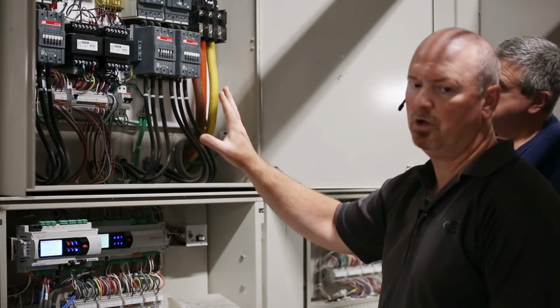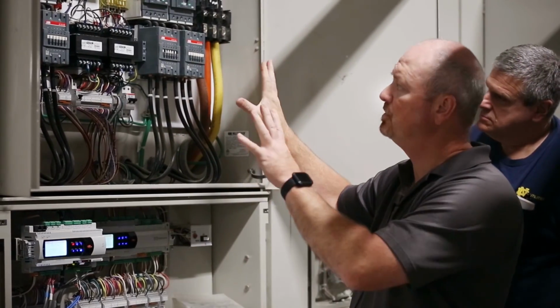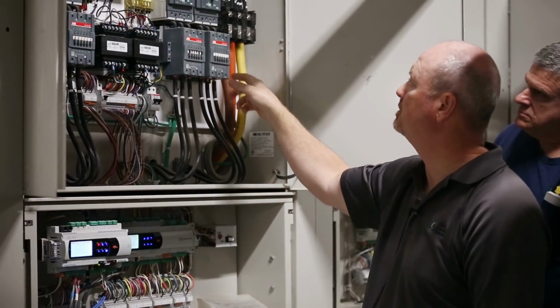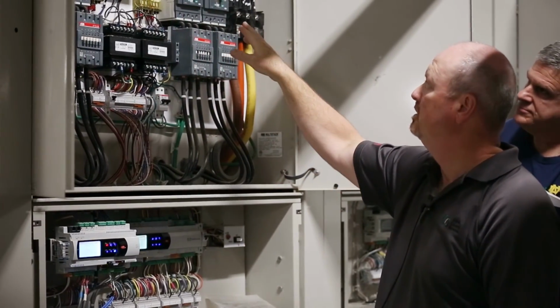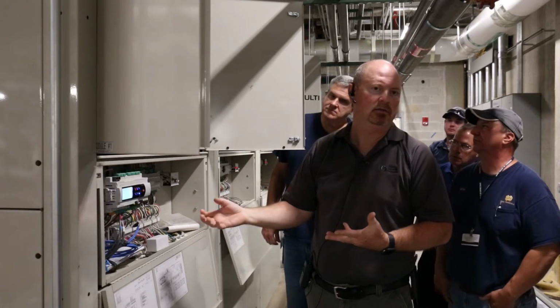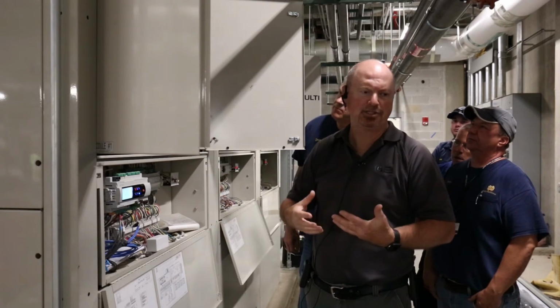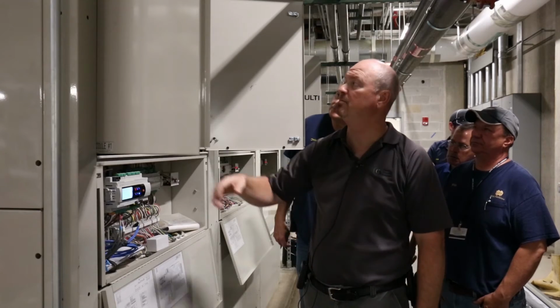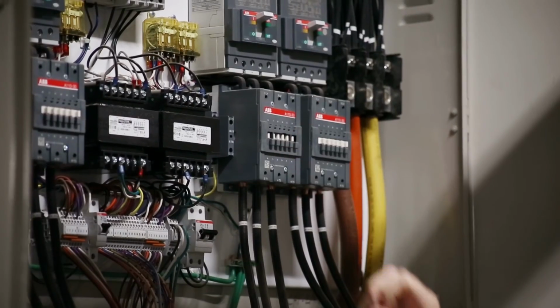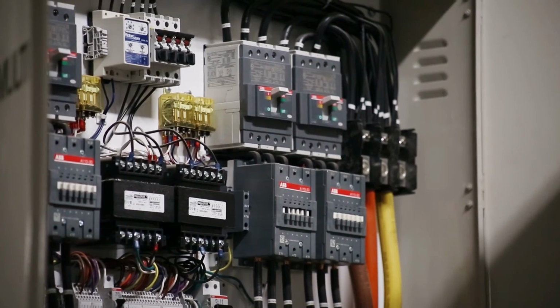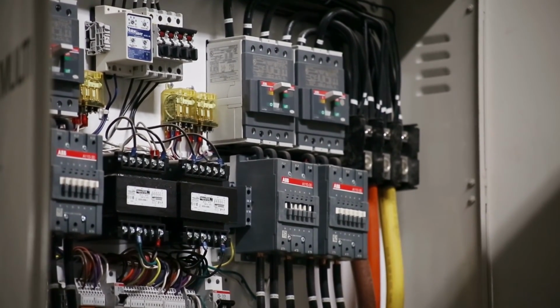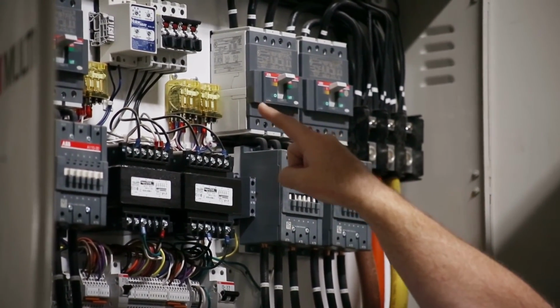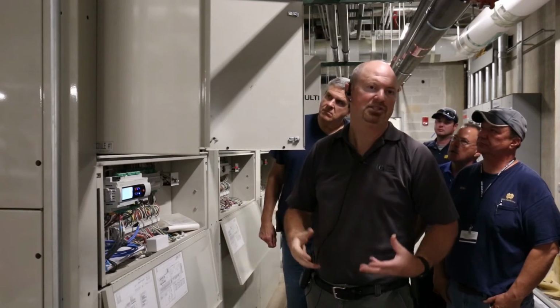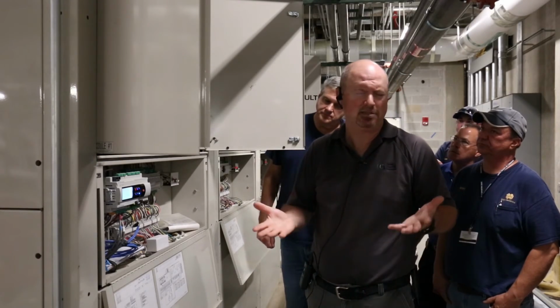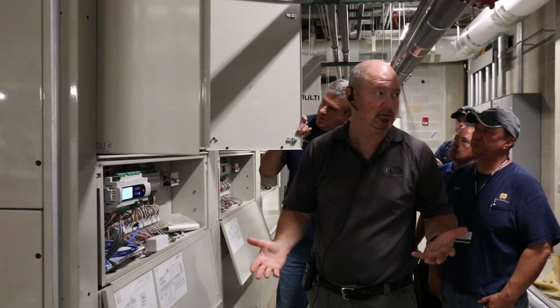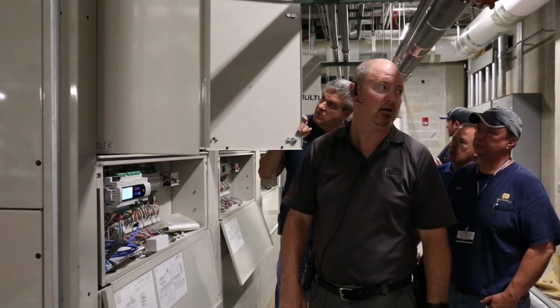This is your controls for each module. 4 compressors, 4 contactors, 4 breakers. If you see one that's tripped on pressure ratio, that means maybe the breaker's tripped on it and the compressor doesn't run, so it doesn't have a good compression ratio. That's usually one of those. Each module has its own phase monitor. You'll see that come across as PPM and you'll be like, what's PPM? It has nothing to do with water. It's phase monitor, power phase monitor.